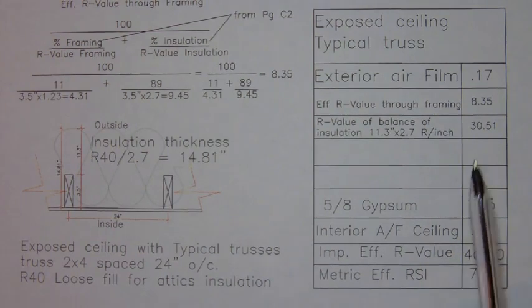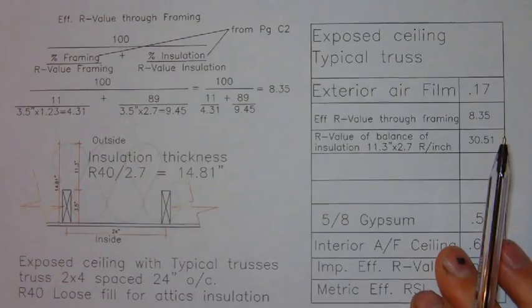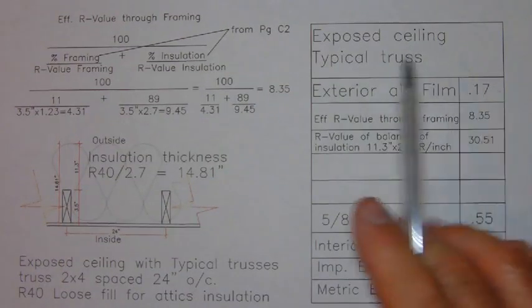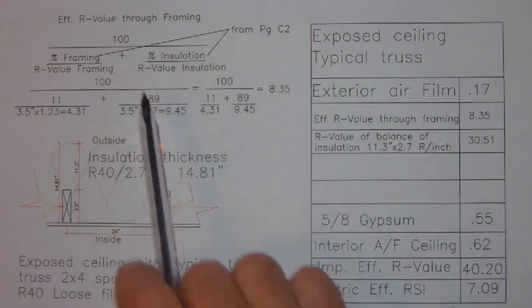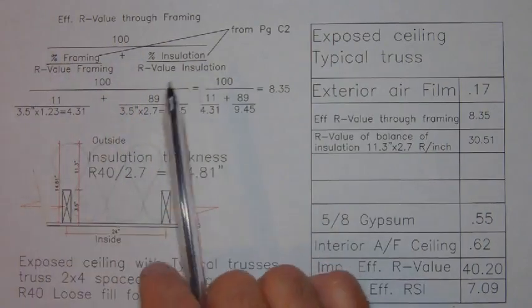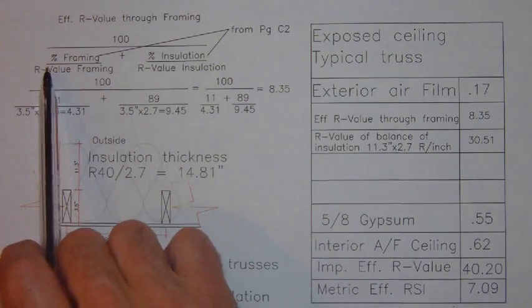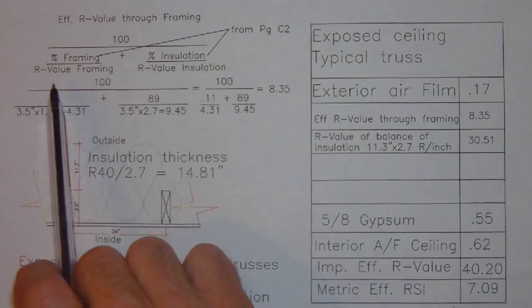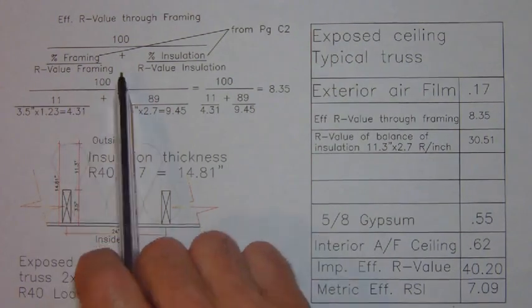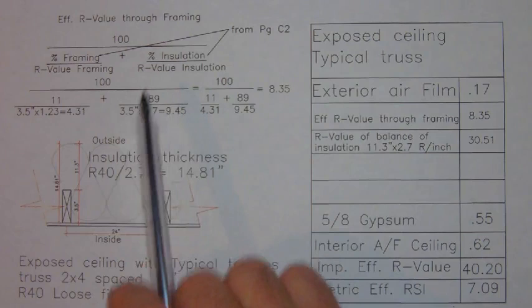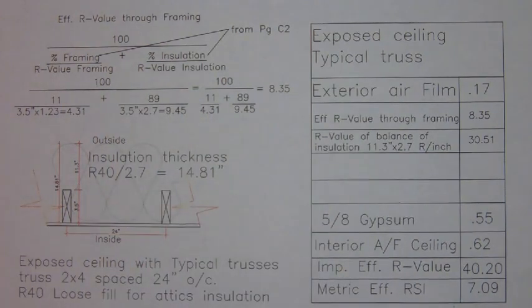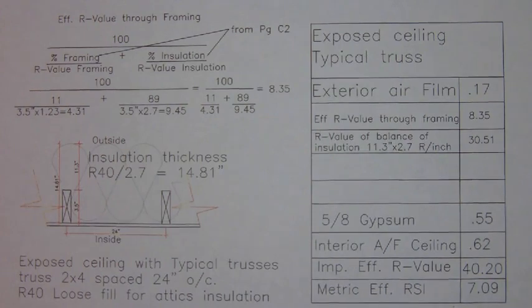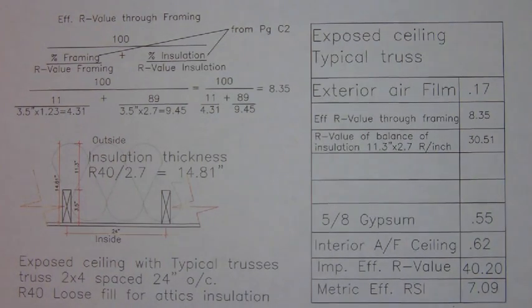So we use a special formula to establish the effective R-value, and we've got this formula up here. 100, all divided by the percent framing divided by the R-value of the framing, plus the percent insulation divided by the R-value of the insulation. And if you were to look on page C5 of your HRAI manual, you should find a table that looks like this.